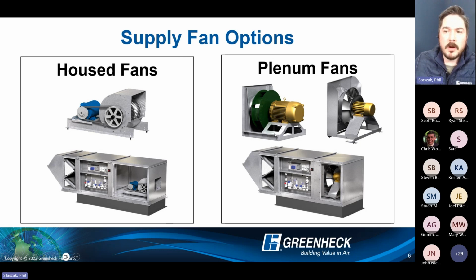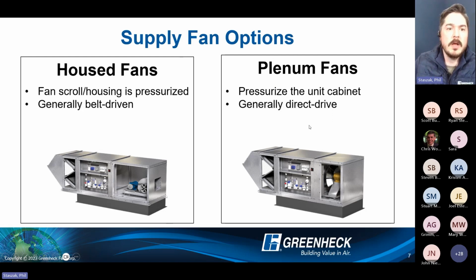We're seeing a shift in the market, and as a manufacturer, all the way up to 25,000 CFM at Greenheck, we have standardized on these direct drive plenum fan offerings now. So with a fan scroll housing, you're pressurizing the actual scroll itself and it's generally belt driven. Where now with a plenum fan, you're actually pressurizing a cabinet. So almost endless discharge arrangements that you can do.